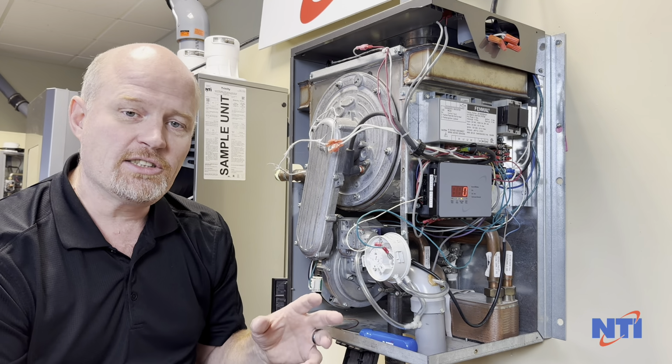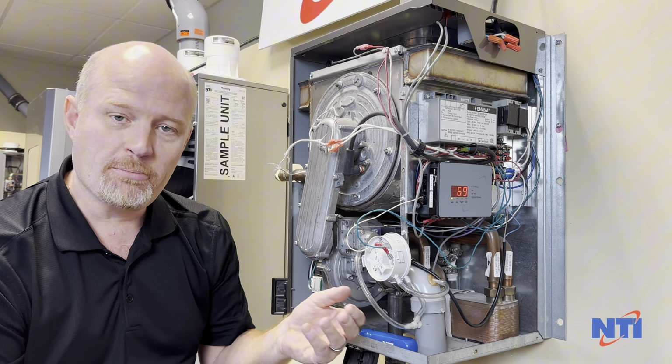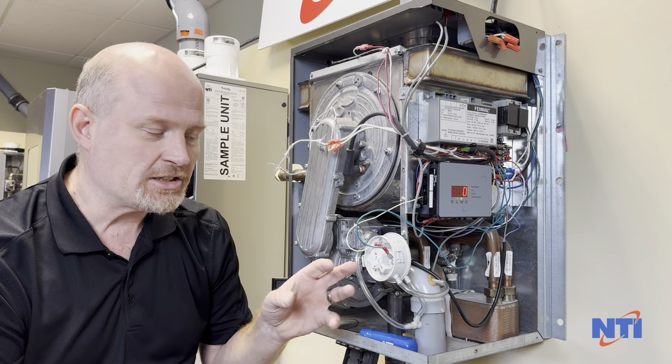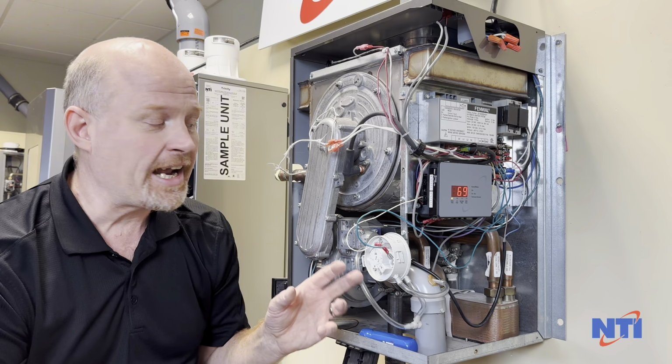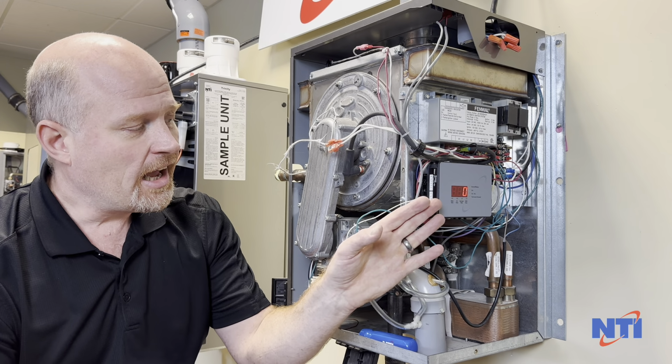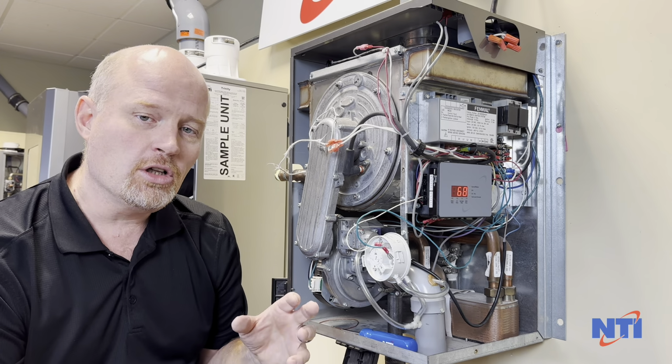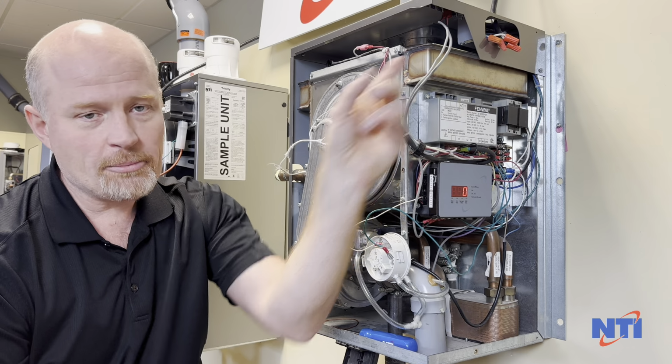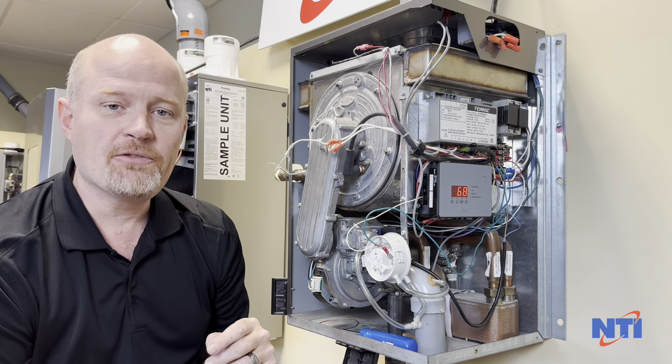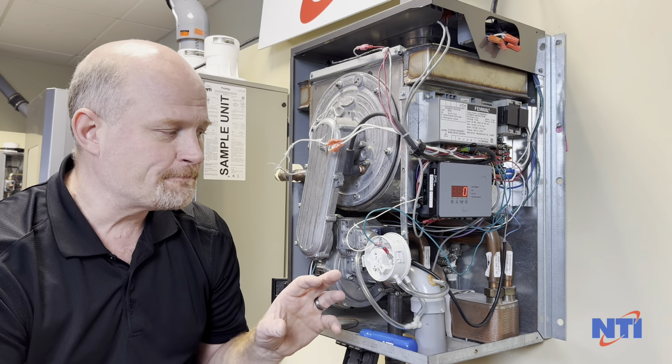There have been cases where an open neutral on a pump or something, or potentially a neutral that's disconnected improperly, can cause this error code. So check all of your neutral wiring, tighten up the wire nuts in the junction box. If there is an external device, bypass it.